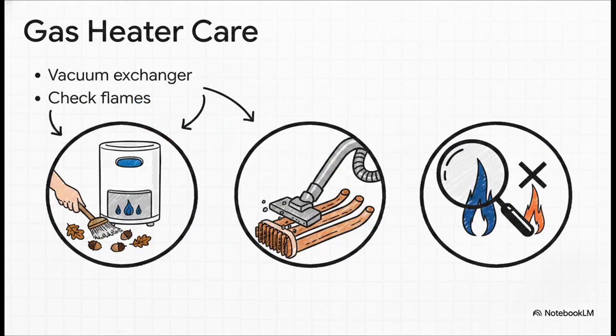Now for gas heaters, it's all about cause and effect. You absolutely must clear the leaves and acorns from the heater floor so the airflow doesn't choke. If it chokes, it overheats and it can literally melt its own internal wires. You'll want to vacuum the copper fin tubes of the heat exchanger, check for internal leaks, and carefully inspect the burner flames. You want a crisp, strong blue color. If you see a lazy yellow or orange flame, well, you've got a serious, potentially dangerous exhaust issue on your hands.